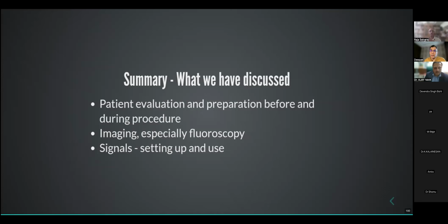So I would imagine there are multiple sources involved there. And again, if I'm not wrong, the J&J system allows you to get signals from the electroanatomical system itself, whereas when it comes to the Abbott system, it kind of bifurcates at the beginning. So you have a feed going into the electroanatomical system and a feed going into the 2D recording system.